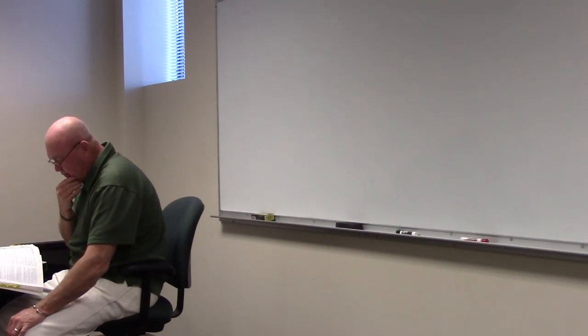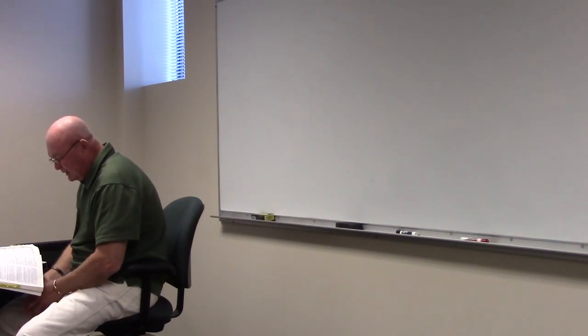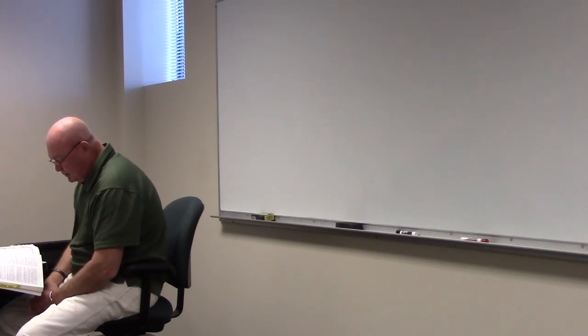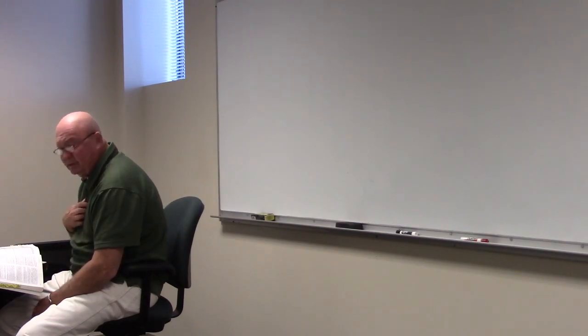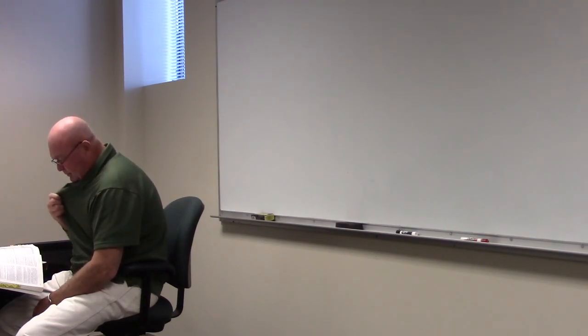So, I've got 250.53, uh-huh. (G). G, there you go. I just found it myself. Matter of fact, I got it highlighted. Must be how deep? 30 inches, yeah, 30 inches deep. Be buried in a trench at least 30 inches deep. The upper end of the electrode shall be flush with the below ground level unless the above ground end and electrode attachment are protected against physical damage.